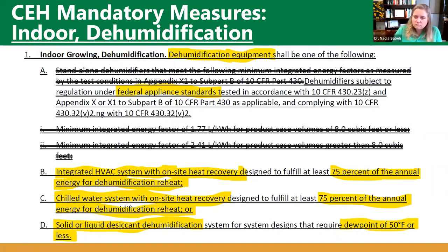Dehumidification should be one of the following. First off, it needs to comply with the federal standards for efficiency based on the testing standards that have been set up. Now, the challenge with dehumidification, as a lot of my HVAC friends know, is that those testing standards are based on residential applications, not on controlled environment horticulture applications. We have a lot of friends in the HVAC industry, equipment manufacturers who are trying to improve these testing standards and get some approved specifically for this application.